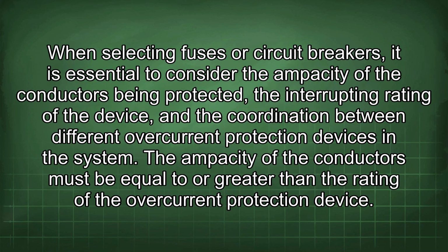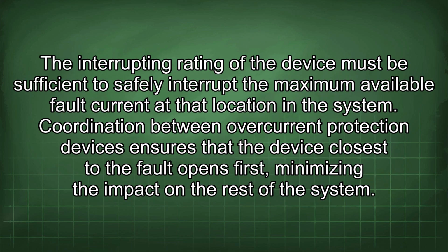They offer convenience and can provide more sophisticated protection features, such as ground fault protection. When selecting fuses or circuit breakers, it is essential to consider the ampacity of the conductors being protected, the interrupting rating of the device, and the coordination between different overcurrent protection devices in the system. The ampacity of the conductors must be equal to or greater than the rating of the overcurrent protection device. The interrupting rating of the device must be sufficient to safely interrupt the maximum available fault current at that location in the system. Coordination between overcurrent protection devices ensures that the device closest to the fault opens first, minimizing the impact on the rest of the system.